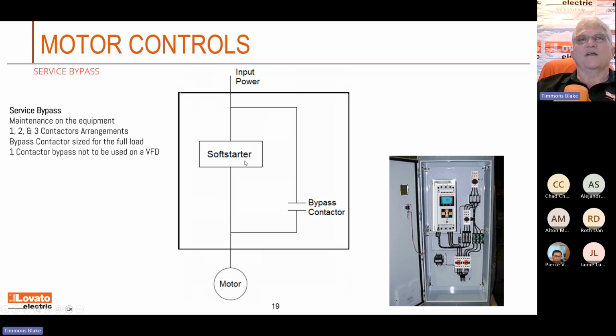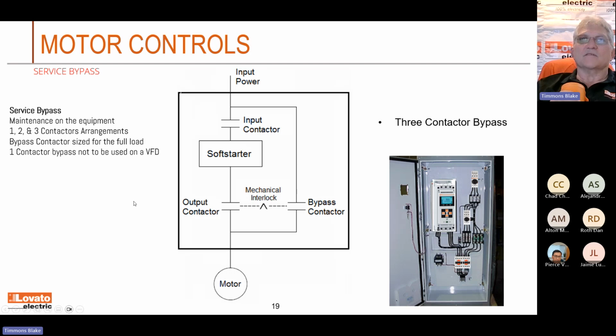That's what this does. So if somebody had a real critical application and that soft starter went bad, they want to be able to turn a contactor on over here and bypass it. So now you have what we call a service bypass. And these come in different flavors. That's a one contactor bypass. You can do a two contactor bypass. Okay. You can do a three contactor bypass. By having a three contactor bypass, you can totally isolate this circuit here where the soft starter was. You can work on it while you have it in bypass. Just a little terminology to be aware of.